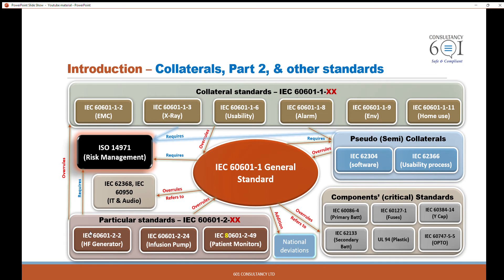On the bottom left we have the particular standards — IEC 60601-2-XX or IEC 80601-2-XX — and those, from the name, are particular to certain devices. I put just three examples here: high frequency generators (dash 2-2), infusion pumps (dash 2-24), and 80601-2-49 for vital sign monitors or patient monitors.